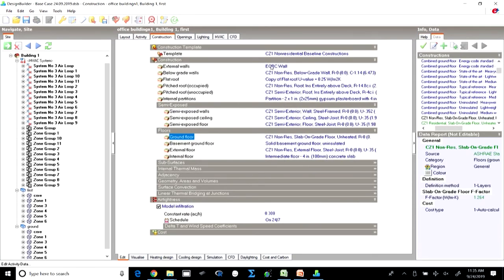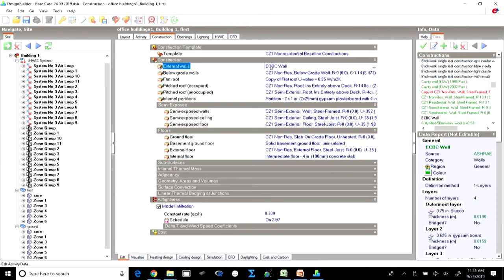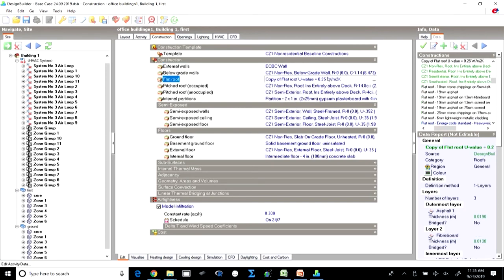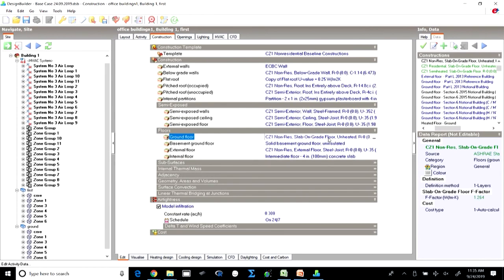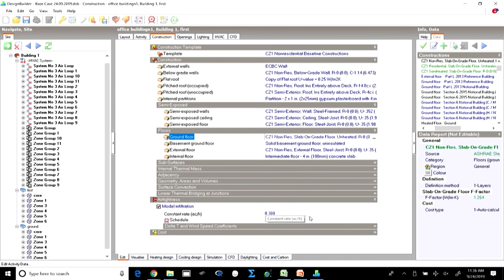We selected the ECBC wall where we specified the U-value, then defined the flat roof where we also defined the U-value — all created as per the prescriptive values suggested in ECBC. Internal partitions were virtual and do not matter much. The ground floor was taken as the default without insulation, so the existing template was used. We also took a constant rate of air changes per hour for modeling infiltration based on ASHRAE 62.2.